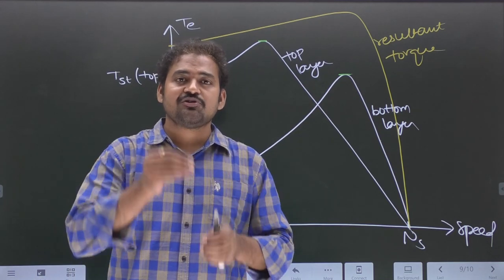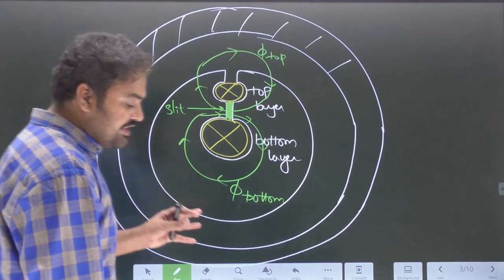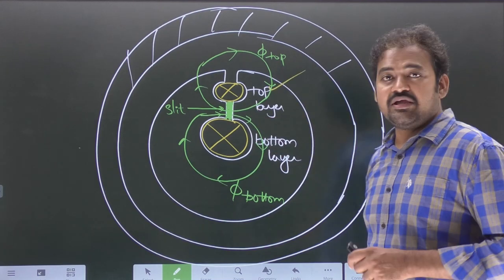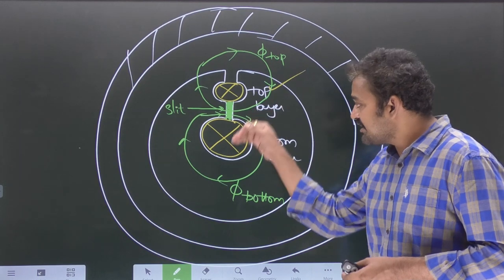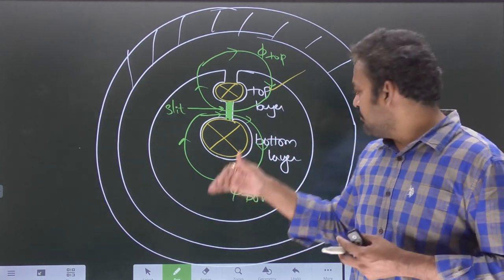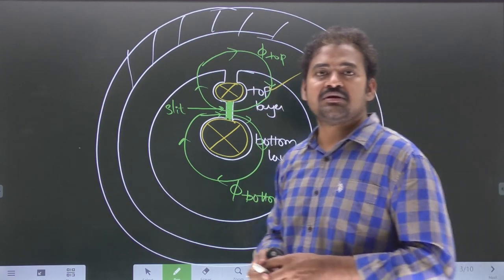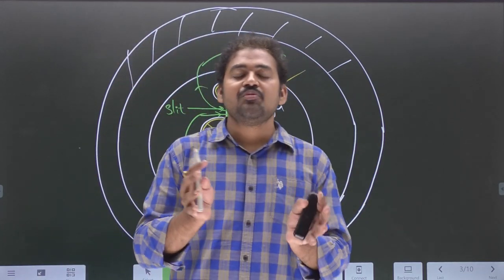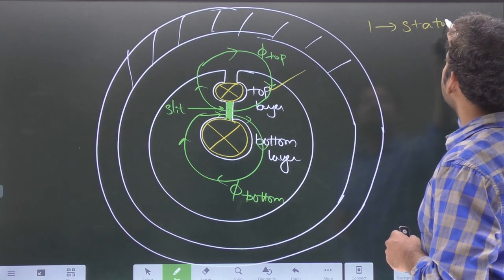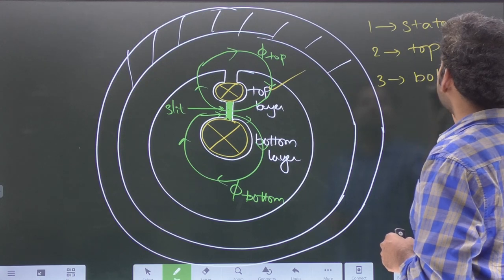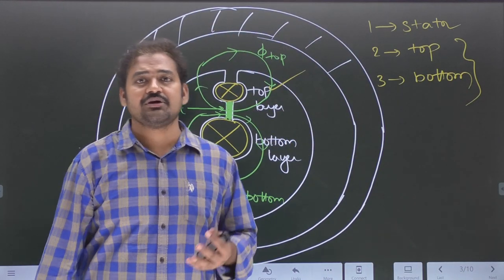In a double cage induction motor, the top layer winding — also known as outer cage winding — offers higher starting torque and lower running torque. The bottom layer winding — also known as inner cage winding — offers higher running torque and lower starting torque. Combining both gives the double cage induction motor. In total, there are three windings: the stator winding, the top layer (outer cage) rotor winding, and the bottom layer (inner cage) rotor winding.